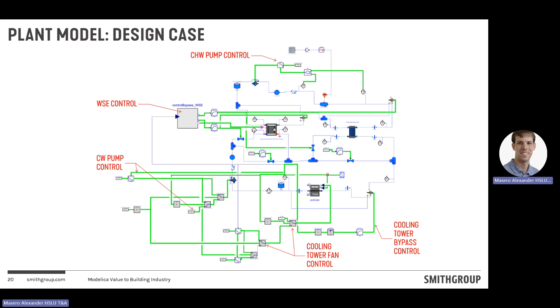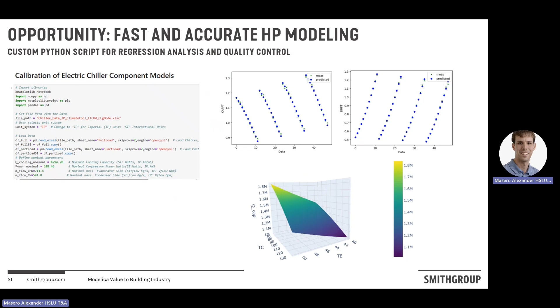Another interesting point: probably the most important parameterization was the chiller, and it's actually quite difficult to get accurate performance data for chillers. Our approach was to spend time gathering over 1,000 points at full and part load and develop regression coefficients. Since the platform is Python adjacent, we were able to pull manufacturer data in, write the regression coefficients, and import them into the Modelica model for more accurate chiller performance.